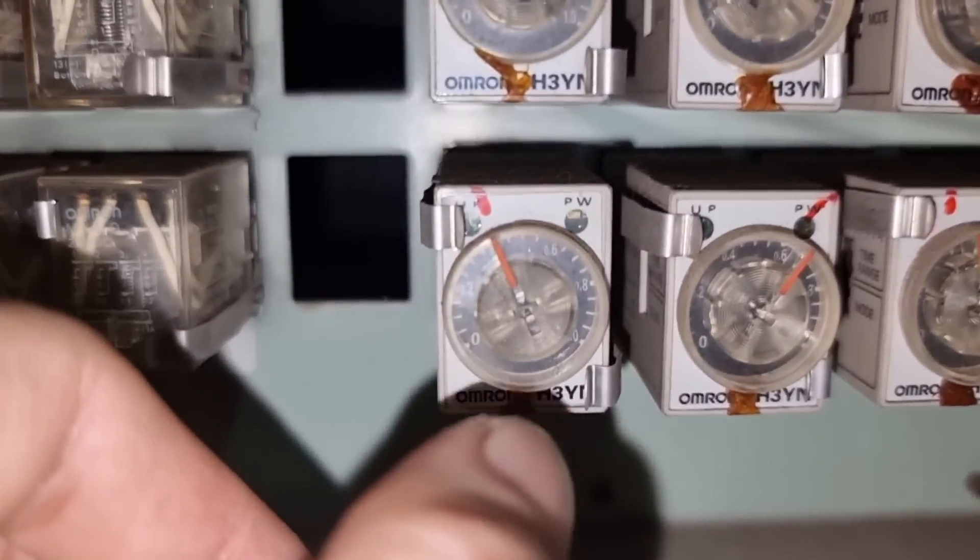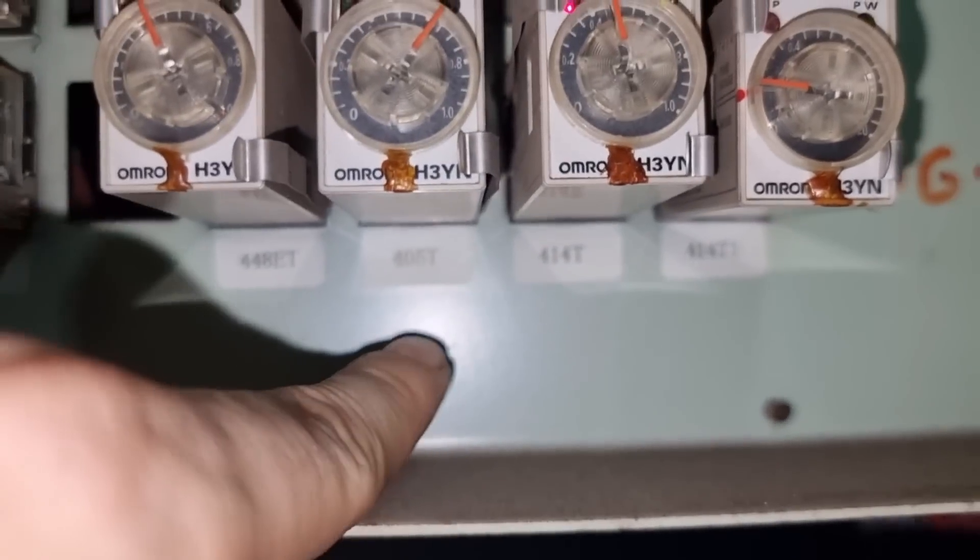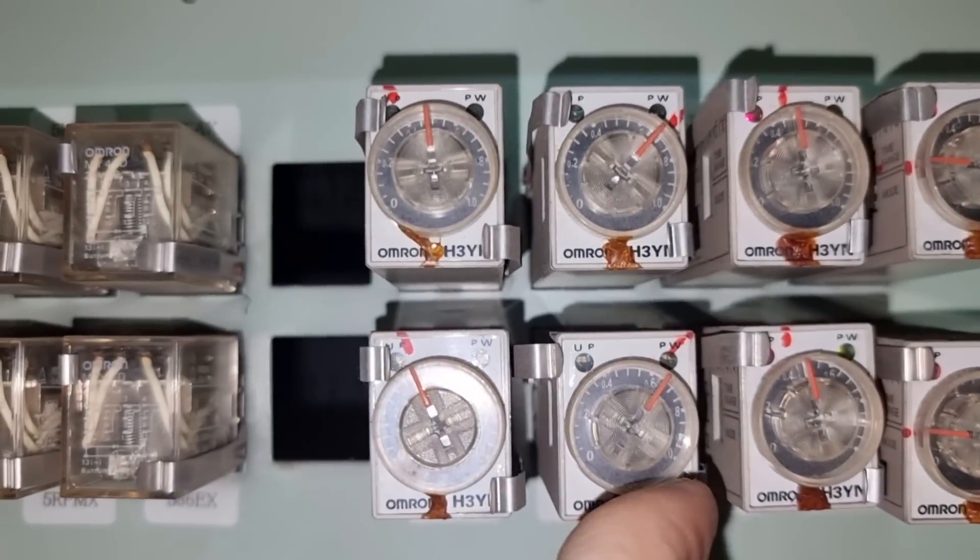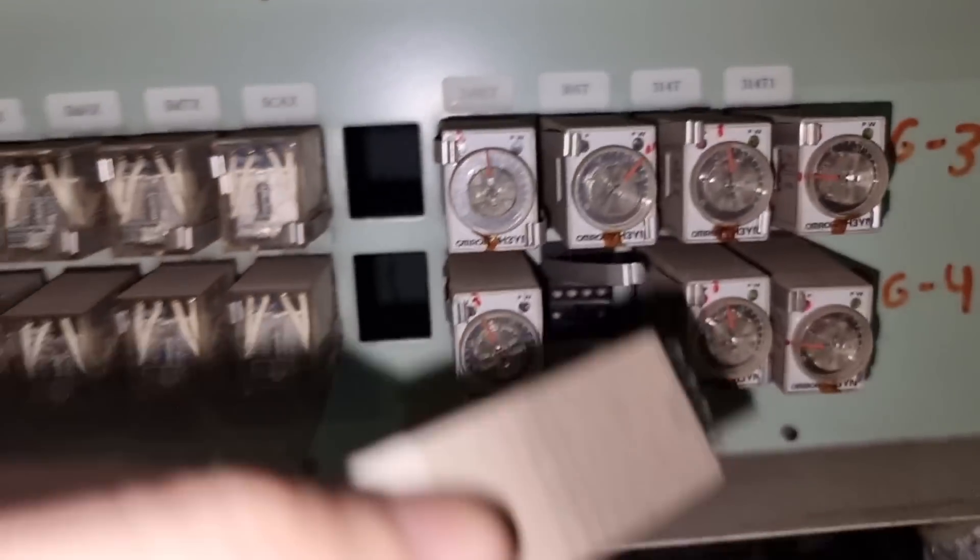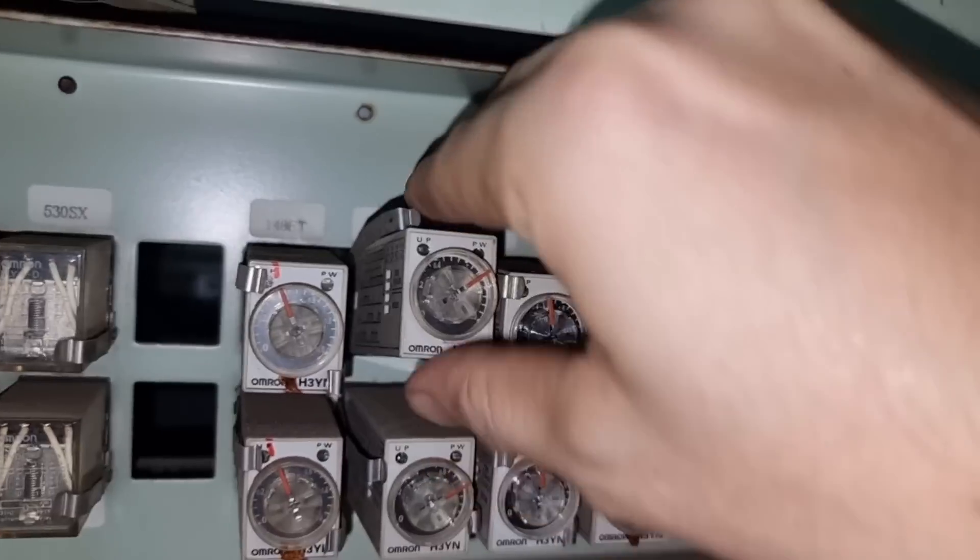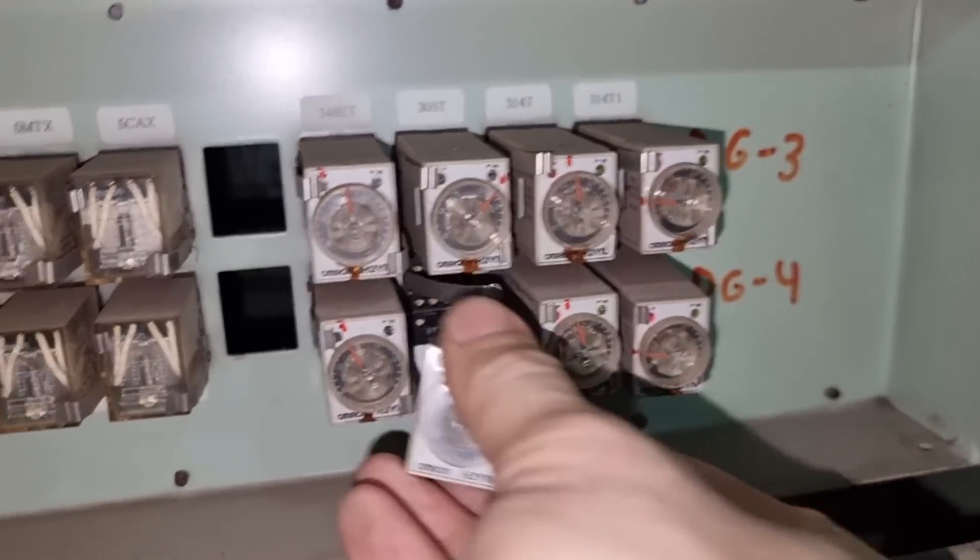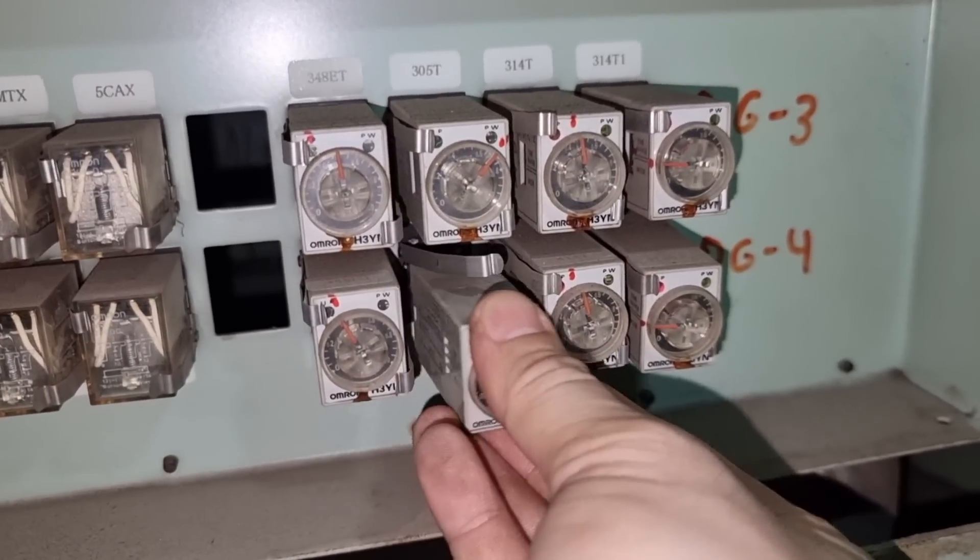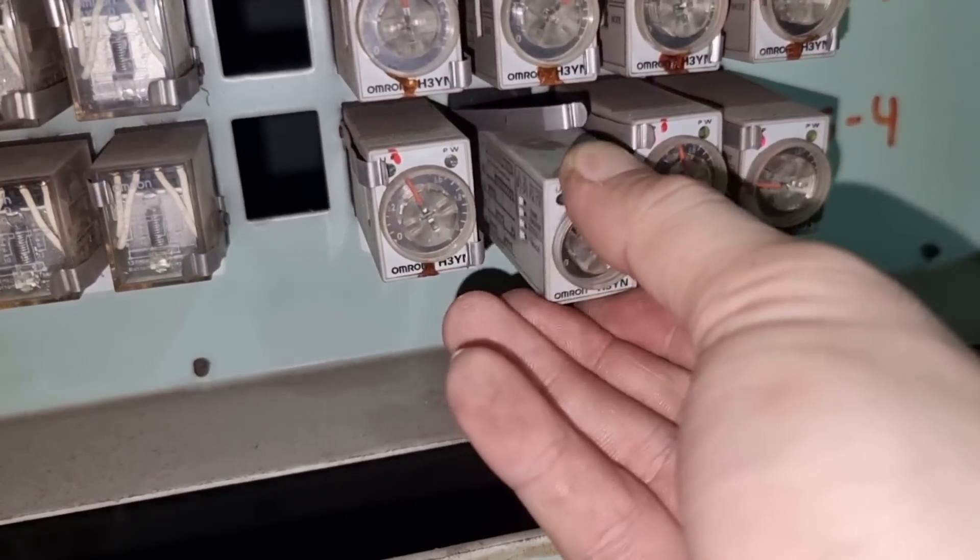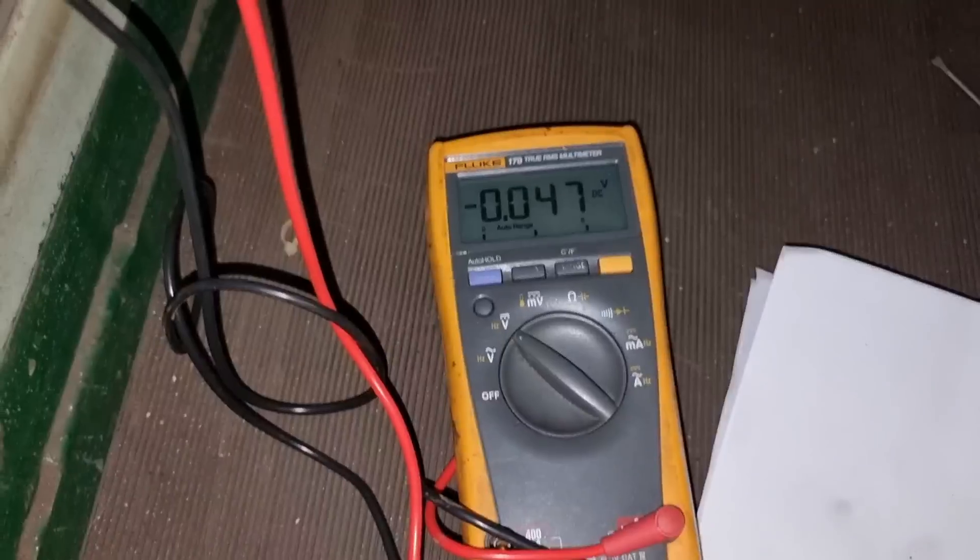To ensure that we have a good contact on this 405T, I will be interchanging this timer of the generator number 4 into the generator number 1. But in this case, or in this way, we will be sure that we have a good timer onto our system. Or at least the contacts for this timer designated for the 405 contactor is really in good condition.